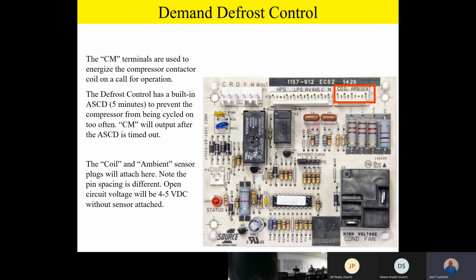One of the things I really like about our Champion and Johnson Controls products here is it's so easy to troubleshoot. If I've got 24 volts on the board and I've got 4 to 5 volts DC on the sensor outputs and I can force a defrost, the board's okay. Anyway, any questions or comments so far?